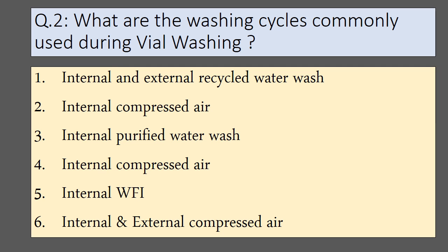The second important question is: what are the washing cycles commonly used during vial washing? There are six washing cycles commonly used. First, internal and external recycled water wash. Second, internal compressed air. Third, internal purified water wash. Fourth, internal compressed air. Fifth, internal WFI. And sixth, internal and external compressed air.